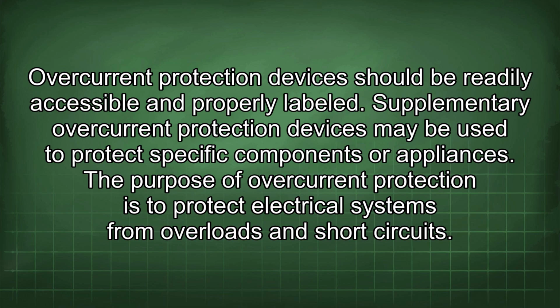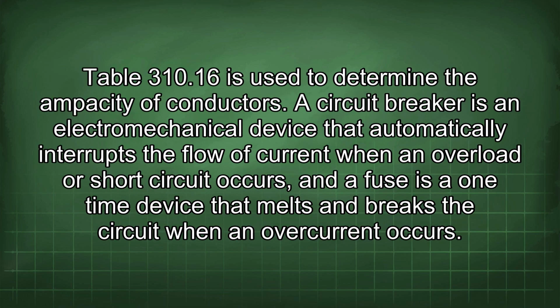Overcurrent protection devices should be readily accessible and properly labeled. Supplementary overcurrent protection devices may be used to protect specific components or appliances. The purpose of overcurrent protection is to protect electrical systems from overloads and short circuits. Table 310.16 is used to determine the ampacity of conductors. A circuit breaker is an electromechanical device that automatically interrupts the flow of current when an overload or short circuit occurs, and a fuse is a one-time device that melts and breaks the circuit when an overcurrent occurs.